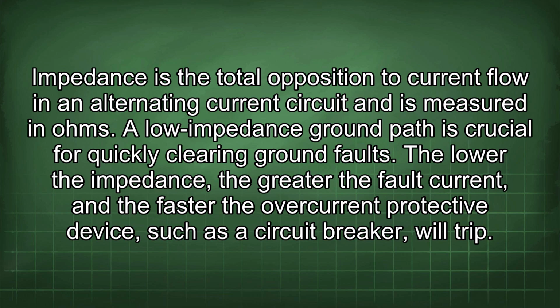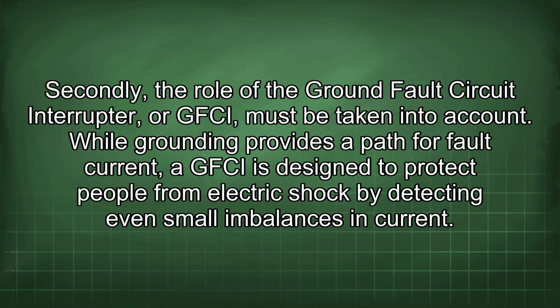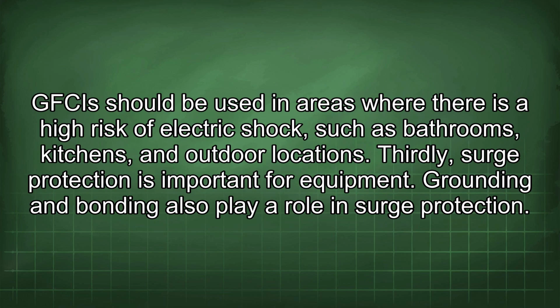breaker, will trip. Secondly, the role of the ground fault circuit interrupter, or GFCI, must be taken into account. While grounding provides a path for fault current, a GFCI is designed to protect people from electric shock by detecting even small imbalances in current. GFCIs should be used in areas where there is a high risk of electric shock, such as bathrooms, kitchens, and outdoor locations. Thirdly, surge protection is important for equipment.